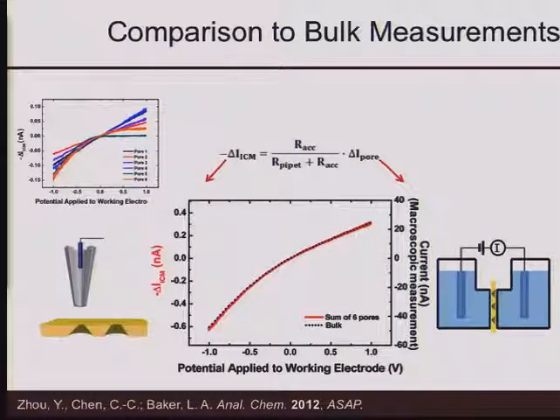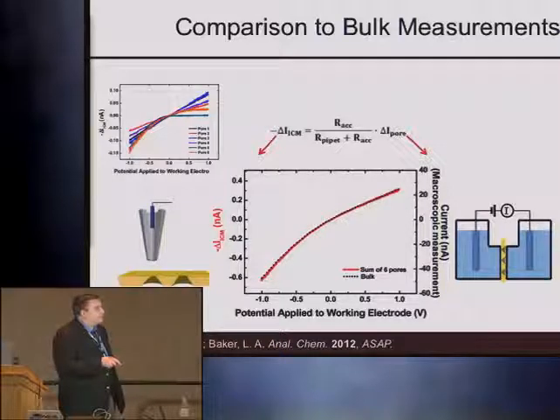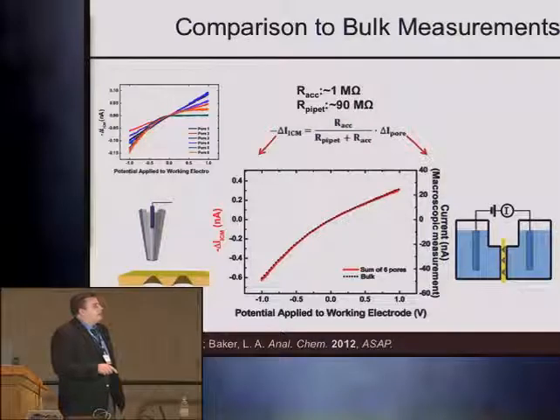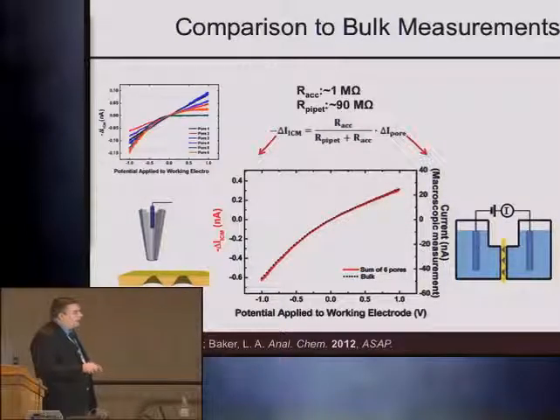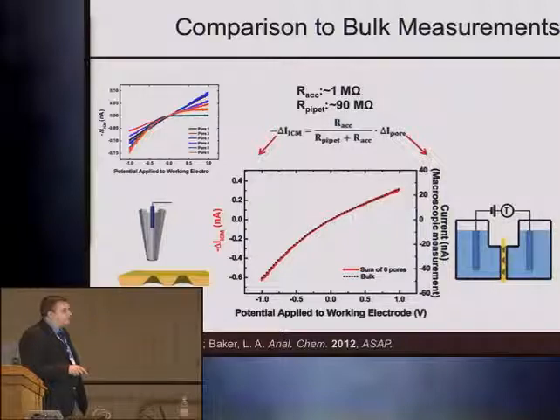Further, if you look at the equation that we developed, the change in the ion conductance microscope current relative to the change in the pore current should be related to each other through the access resistance and the pipette resistance. If we plug in values that are realistic for this system, an access resistance and a pipette resistance of 1 megohm and 90 megohms, you can see that these two values on the y-ordinates are very close. The y-axis in this case is about 1% of the y-axis in that case, and that agrees very well with these numbers.